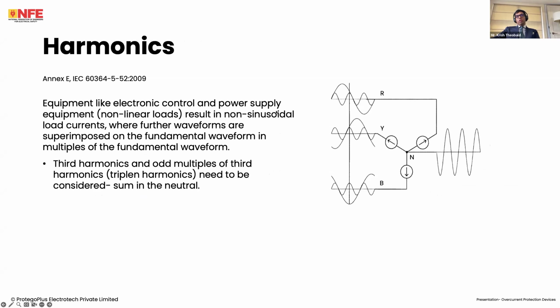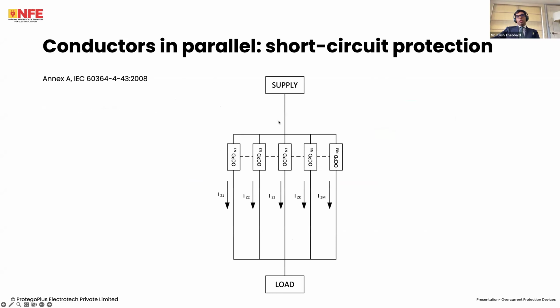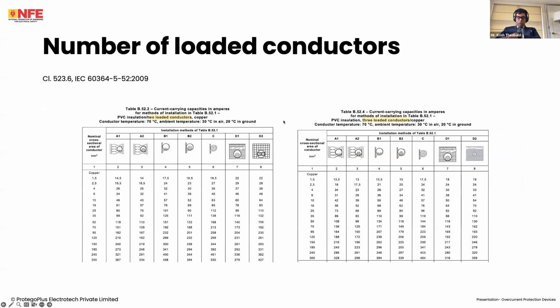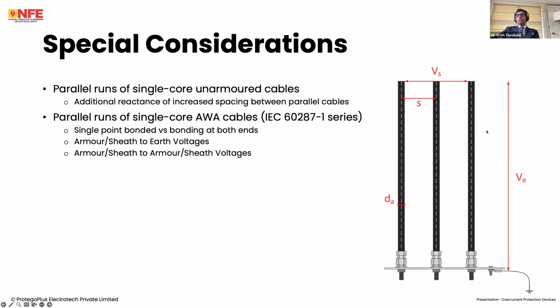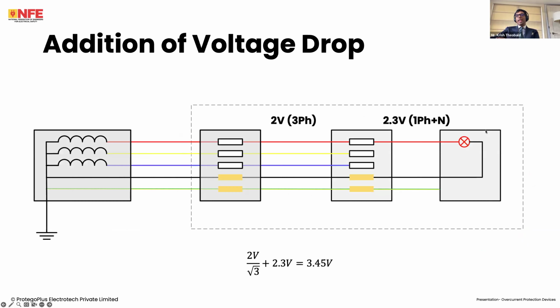Now, like I mentioned earlier, I will just go back. Conductor current carrying capacity is based on the number of loaded conductors. So for a three-phase circuit, it is three loaded conductors, but we actually have four loaded conductors, because it is only considering lines L1, L2, L3, but not considering the neutral being loaded, because we are now in effect grouping a fourth loaded conductor with this circuit. There a reduction factor has to be taken into account to come up with the current carrying capacity. That is this 0.86 value that I showed you here.